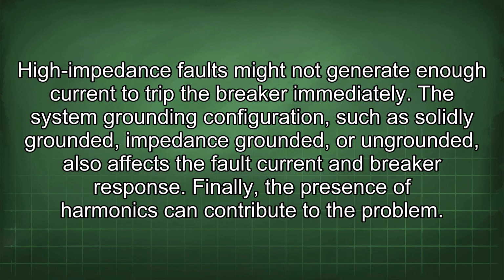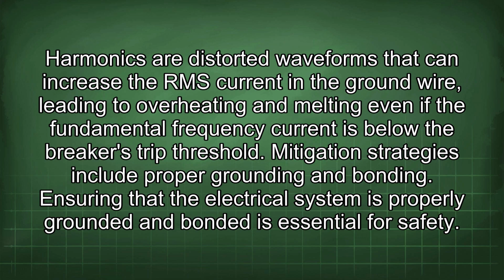Finally, the presence of harmonics can contribute to the problem. Harmonics are distorted waveforms that can increase the RMS current in the ground wire, leading to overheating and melting even if the fundamental frequency current is below the breaker's trip threshold.